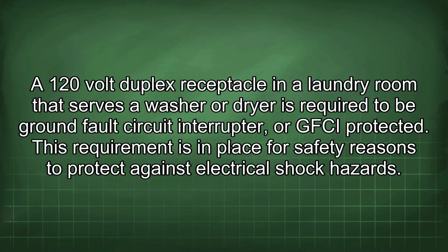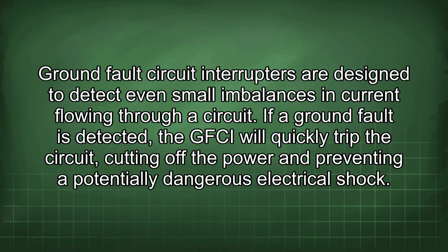A 120-volt duplex receptacle in a laundry room that serves a washer or dryer is required to be ground fault circuit interrupter, or GFCI protected. This requirement is in place for safety reasons to protect against electrical shock hazards. Ground fault circuit interrupters are designed to detect even small imbalances in current flowing through a circuit.